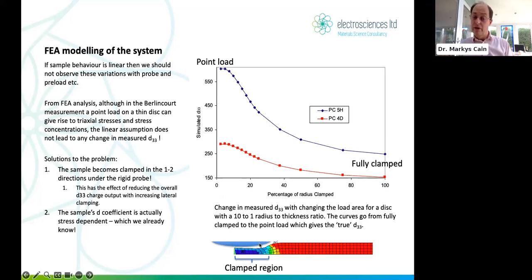Now, when we apply a load under this hemispherical domed electrode, that's not moving. That X and Y, it's not moving, which means when it's in contact with the sample, especially if the sample's a thin film, then that part of the film is clamped. It's not able to move in X or Y. It wants to move in Z and generate a charge, but it can't move as much in Z as it wants to because its X and Y is clamped. Okay, this is a big issue in any thin film work, thin film piezo ferroelectrics. Everyone on this call probably knows that, but it's also an issue here. Therefore, this effect here of the d33 that you might measure as a function of how much you're clamping that piece of material. In other words, what's the region of stressed area of stress material?